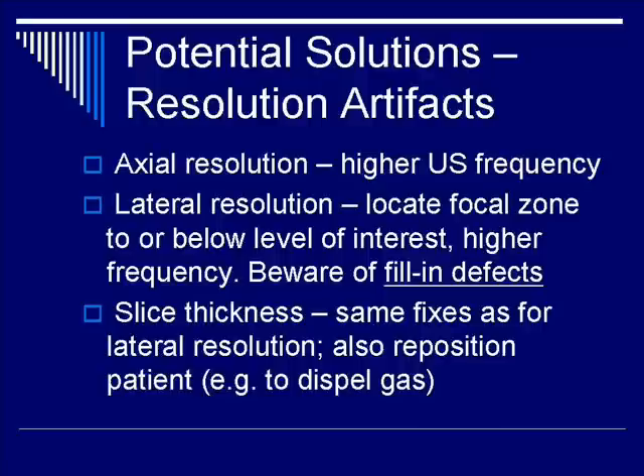In summary, in terms of resolution artifacts, the potential solutions are: for axial resolution, use high ultrasound frequency as tolerated — though you lose penetration depth. For lateral resolution, locate the focal zone at or below the level of interest and use high frequency, but beware of fill-in defects. For slice thickness, use the same fixes as for lateral resolution — high frequency — and also reposition the patient to dispel gas.